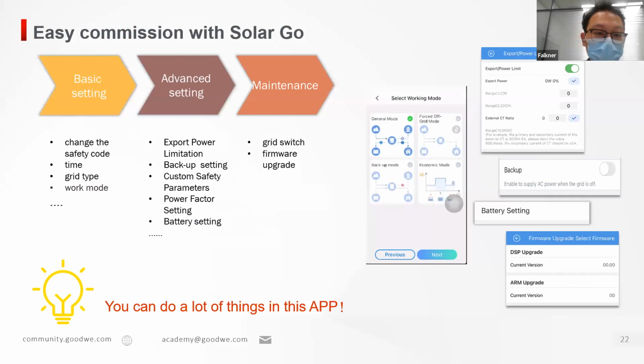Next is our commissioning. You need to set the basic settings to change the safety code, check the time and the grid type, and set the work mode. Next is the advanced setting. You need to set the export power limitation and the backup setting. Also, some custom safety parameters and power factor setting. Next is maintenance. You need to set the grid change and update your firmware.